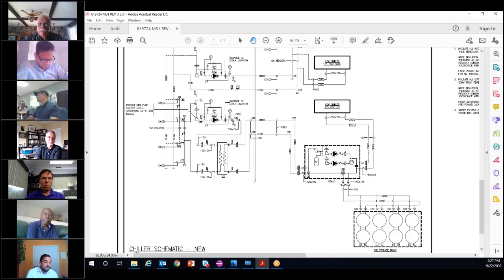So these tanks are essentially frozen overnight when the dollar per kilowatt hour rates are very low. And then during the day from about noon to 7 o'clock, which is when the hospital sees their higher utility rates, that's when we turn a chiller off and use as much ice as possible for those 6 or 7 hours, using one chiller at part load to top up any additional capacity that's needed. And in doing so, significantly reducing the monthly and annual kilowatt hour cost that the hospital sees on their utility bill.